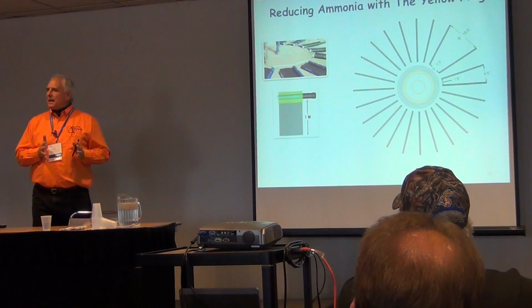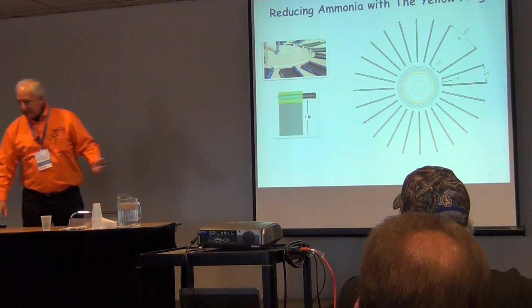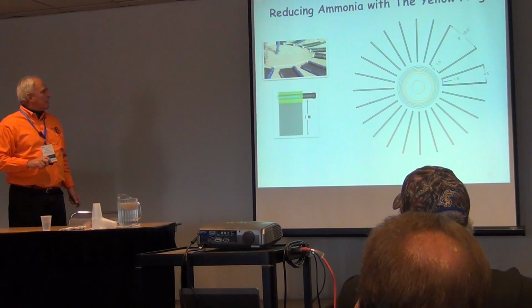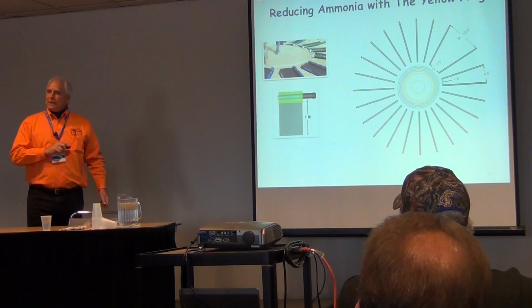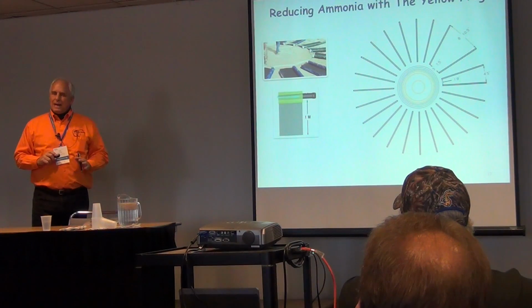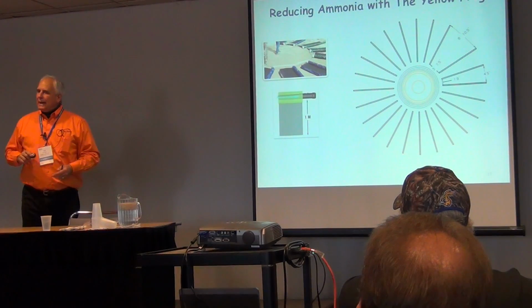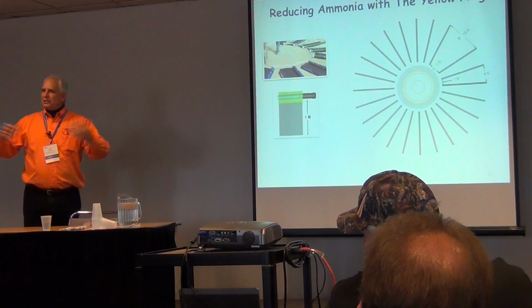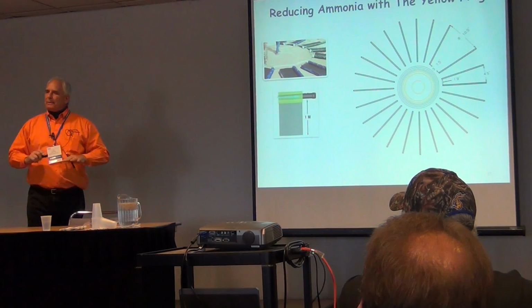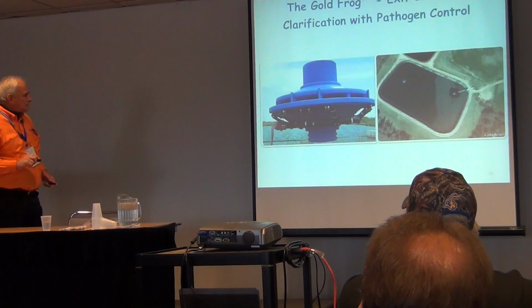But when you have these grazers and shavers there, what they really do, they take suspended solids, which are hard to settle, and they make worm castings, which are heavy. And then the worm castings come down, and they feed the biofilm granules down at the bottom, and you get rid of the ammonia, and you get rid of the carbon as well. And you can put this up in the high carbon part of the zone, which all the books say you can't do. The reason you can do that is because with return activated sludge, you're at very, very high suspended solids levels. And that means those are mostly carbon, and they consume all the oxygen. But when you have grazers that graze down the population, so all of them are population limited, then you have plenty of oxygen for both the carbon and the nitrification.